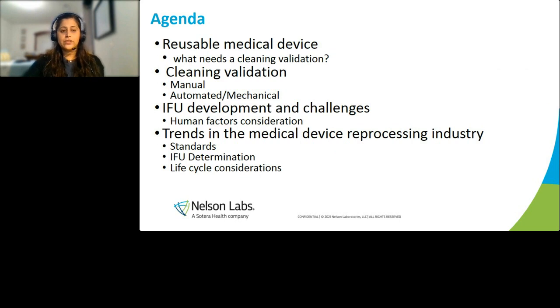For the agenda, I will be going over reusable medical devices, what needs a cleaning validation, right? That is one topic that the industry still needs a little updating on, because a lot of times we do see manufacturers say, hey, do we really need this for this type of device, or for non-critical devices that are not patient affecting? And so those are the things that I will talk about. What entails in the cleaning validation? We have manual, we have automated, IFU challenges, how are human factors considered in these validations, and trends in the medical device industry regarding cleaning, regarding IFU and life cycle. So we'll go through all this today, and hopefully after this session, you will come out with a better understanding of what it takes to perform these validations and bring it over to the user side where they're actually performing these every single day.